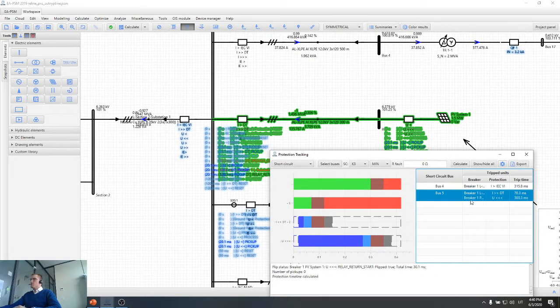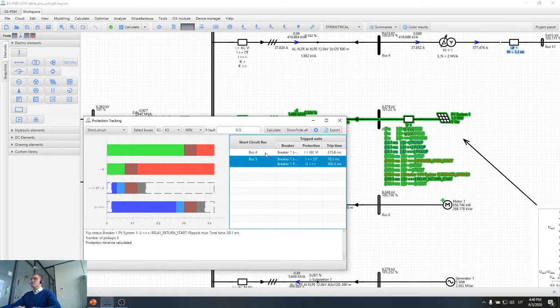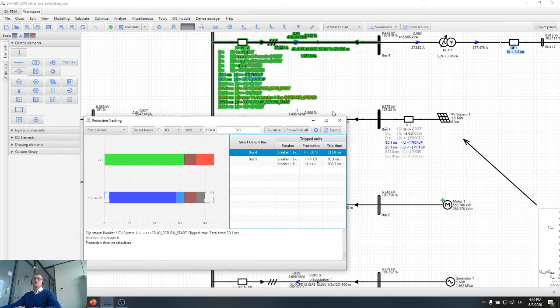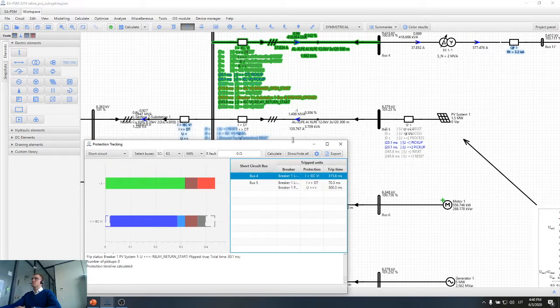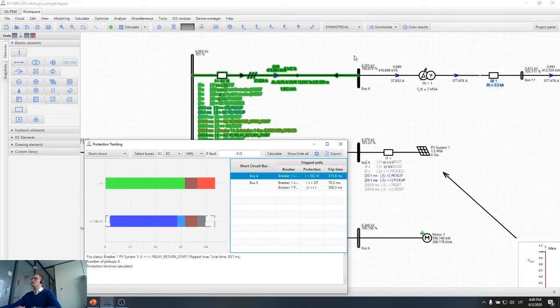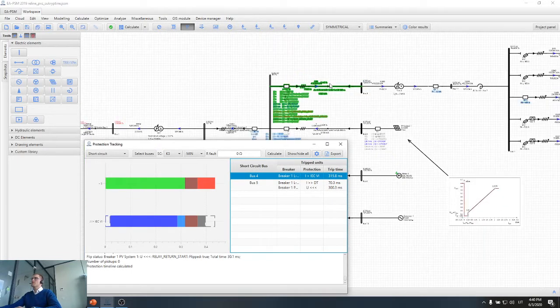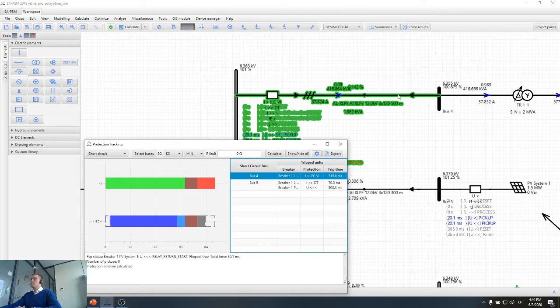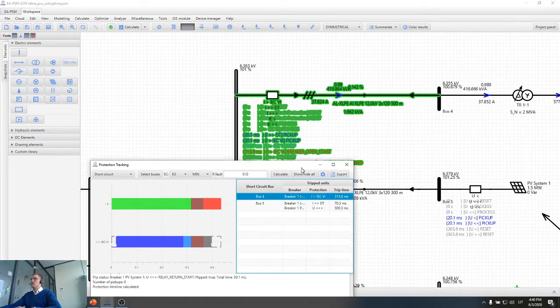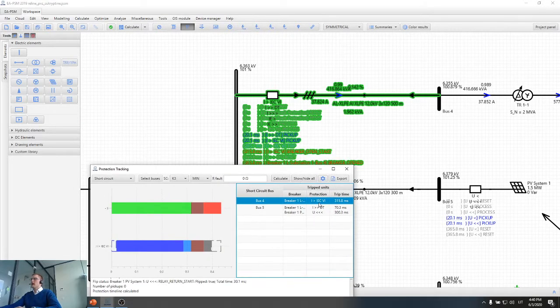So when we do this kind of simulation, software provides information about what are the protection devices tripping in each case. So if I have short circuit at bus 4, I can see that this line has tripped, and the protection device which has tripped is IEC very inverse curve. So this curve tripped in this protection device in 315 milliseconds.